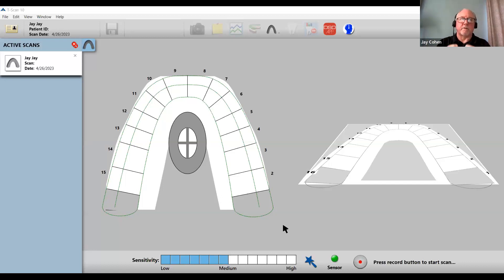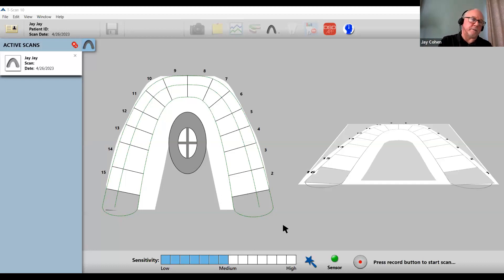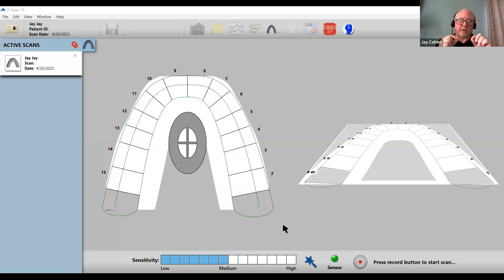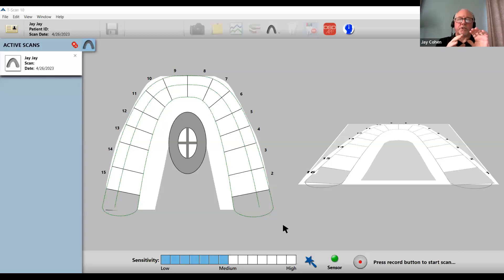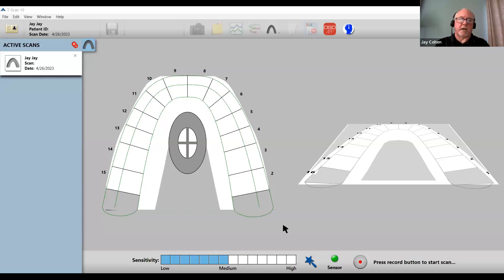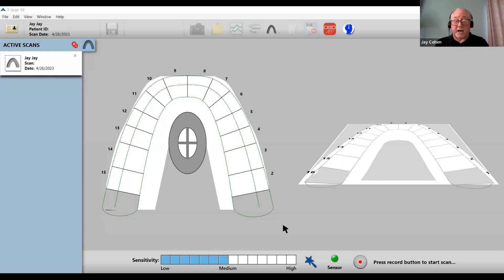I have a question from a participant: Do you suggest to start at medium or high sensitivity to get the best reading? I suggest you start at medium, level seven of 14. Typically, it's going to be a couple of clicks up or down from the middle. Unless you have a really super strong bite, or a patient with less tooth contacts, you might have to set it way down. If a patient has a good even bite or good distribution around the arch, the forces will tend to distribute out more evenly, and you probably would tend to set the sensitivity higher.